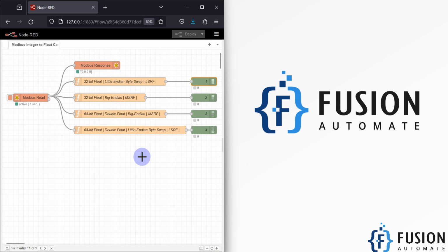If I open my flow, you can see I have created a function for four types of floating point values. The first type is 32-bit float, which is a Little-Endian Byte Swap type, also called least significant register first. The second one is 32-bit float, Big-Endian, most significant register first. The third one is 64-bit float. So the first two are 32-bit float values and the second two are 64-bit float values.